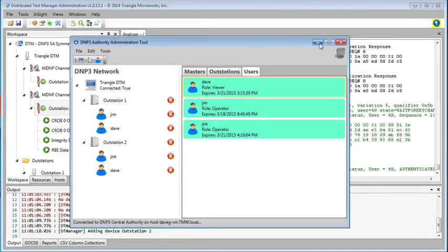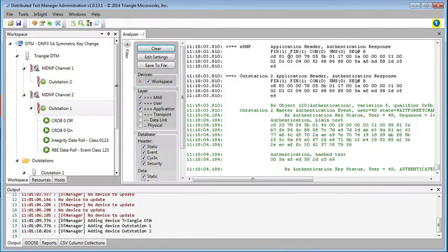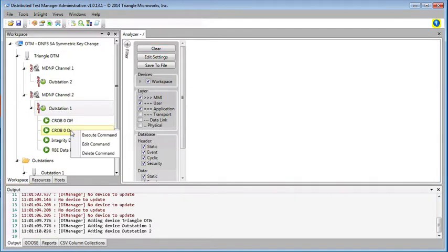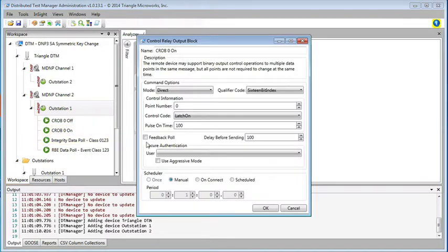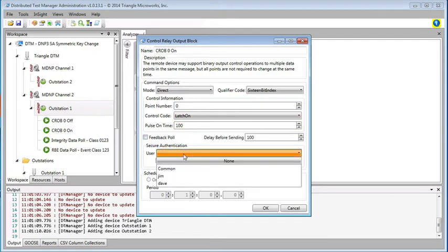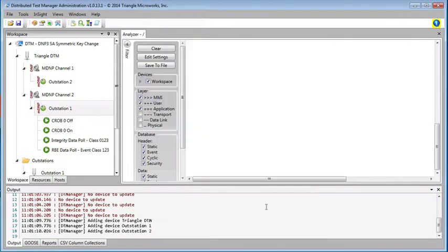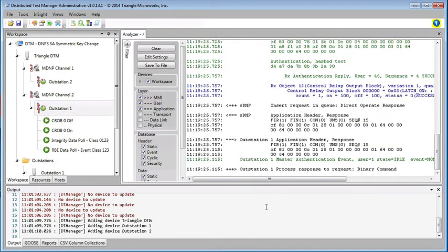So now let's see that in action. If we go to the DTM, go to outstation 1, and we're going to send a CROB command. We'll send the latch-on command, and we can choose one of the assigned users. Let's choose Jim, since he's assigned to be able to send controls. He's an operator. Say OK. And we see that the command succeeded.